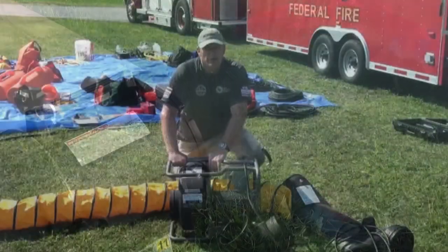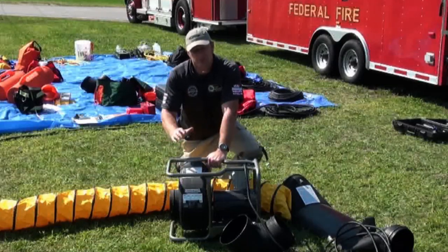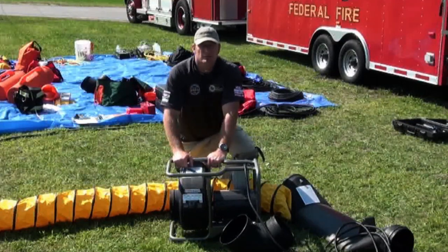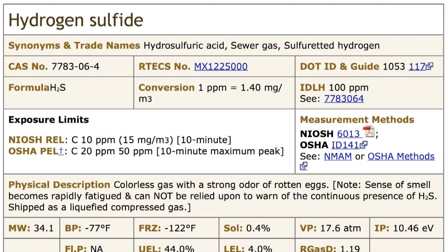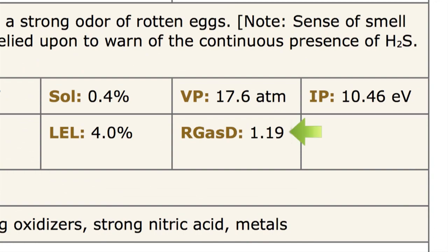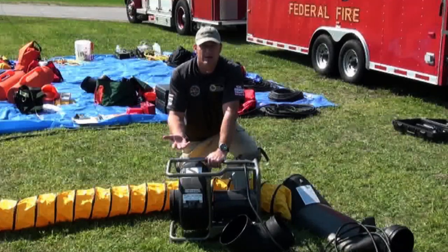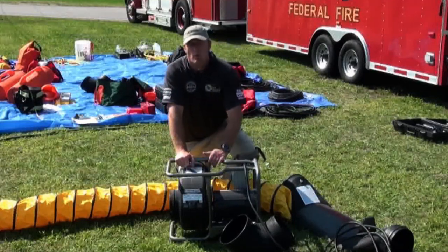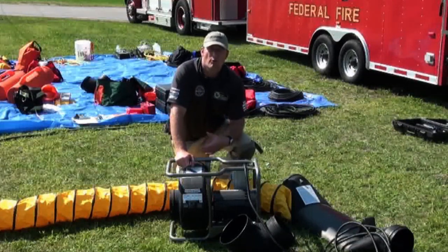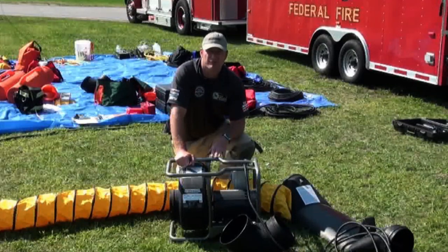When we start, we want to know what we're getting into hazard-wise. One of the primary things we need to assess from a gas perspective is the RGAS-D rating on that hazard. For example, hydrogen disulfide has an RGAS-D of 1.19. If we know that weight is heavier than our standard air weight, we know that hazard is going to be at the low-lying area of that space. When we apply our ventilation, using positive and negative pressure in succession, we want to make sure our ducting reflects the weight of that hazard and how we want to extract it from the space.